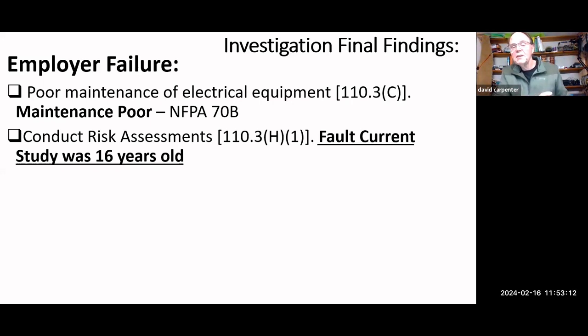If you change out a motor or change out equipment, you need to do an arc flash study right then. So one of the things we've done is take the formulas in the background and put them together into something as simple as an Excel spreadsheet for the employer. So when the employer gets it, if they have to change out a piece of equipment, they don't have to call us.